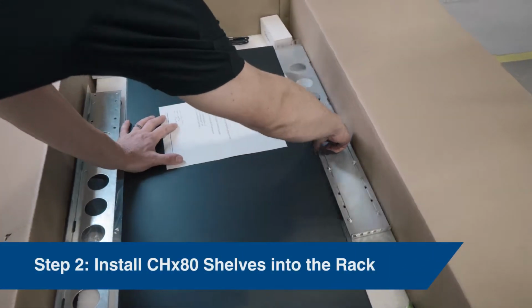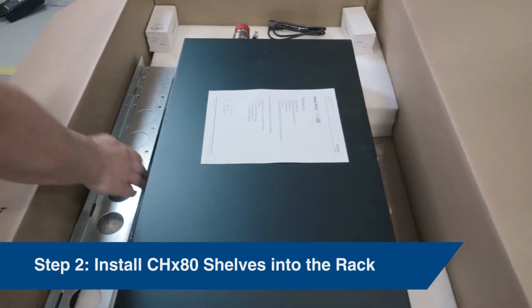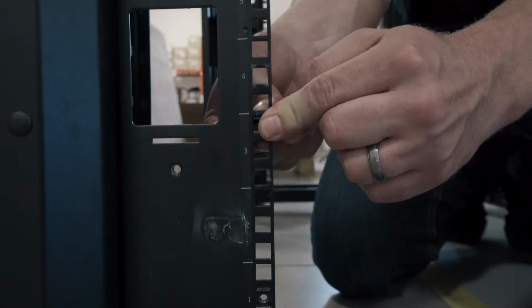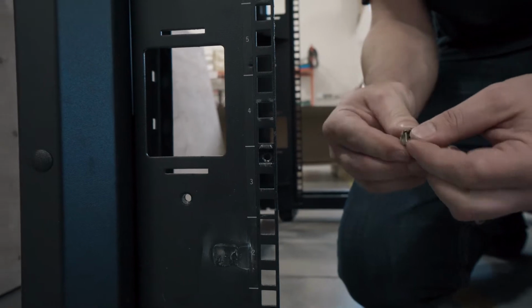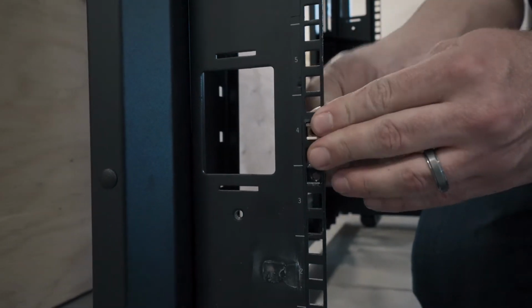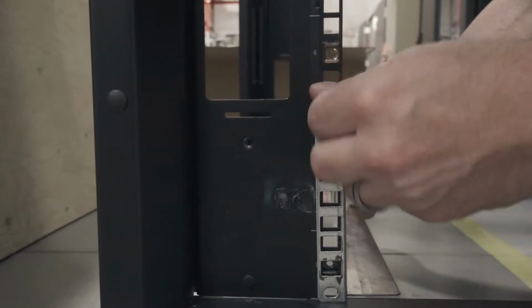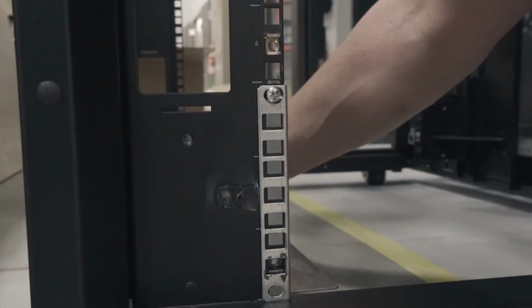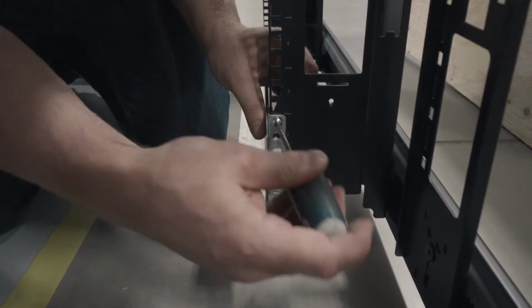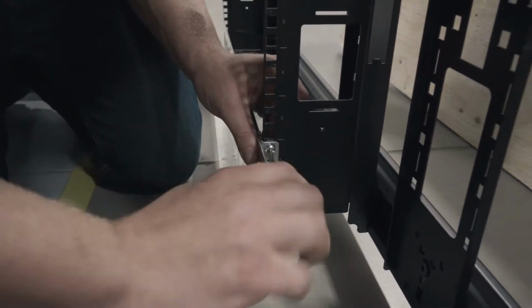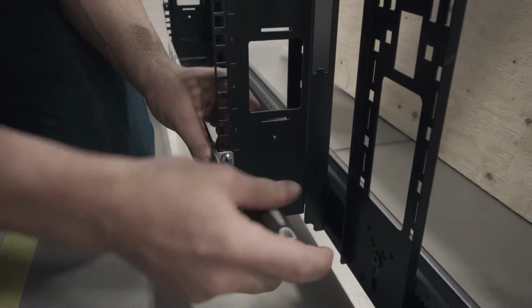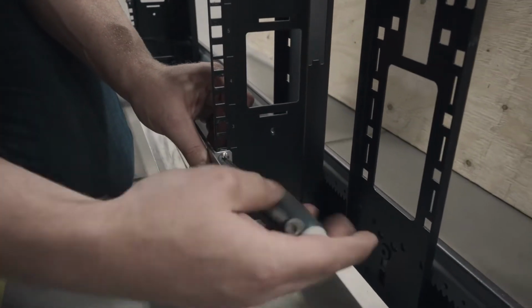Step 2. Install CHX80 shelves into the rack. The heat exchanger ships with IT shelf brackets that must be installed into the rack. Install these shelves into the rack with your drill and number 2 Phillips bit. Position the shelves in the bottom or top of the rack, depending on where the heat exchanger is required for operation.